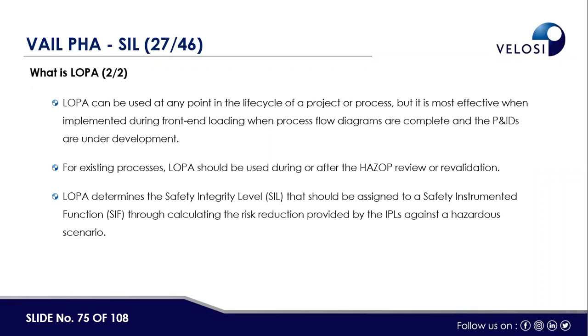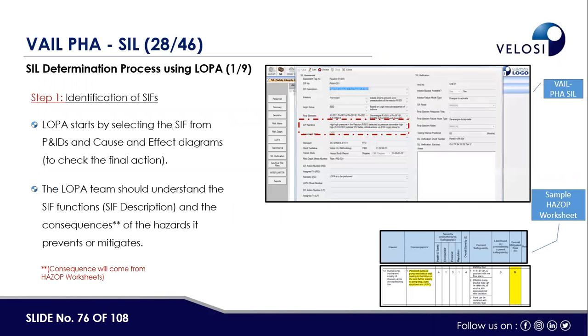LOPA determines the safety integrity level that should be assigned to a safety instrumented function through calculating the risk reduction provided by the IPLs against a hazardous scenario. So now let us go through the stepwise methodology of LOPA.